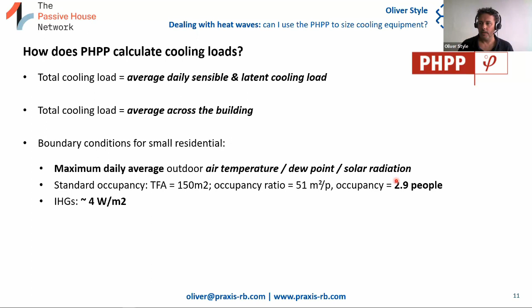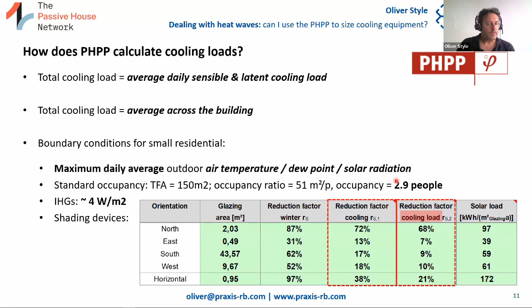And then shading devices. The PHPP calculates a reduction factor for the cooling load that actually assumes that people close the blinds more because it's too hot, and takes that into account for the cooling load. Okay, which you could say is a reasonable and logical assumption. But it's also possible that people don't drop the blinds. They forget to, or there's no control system that does it automatically, or simply they've been away for the weekend and they forgot to pull the blinds down, and they get back on a Sunday afternoon and the whole place is roasting. So it's important to understand what these base boundary conditions are for the PHPP, because they may not correspond to, will often not correspond to, what people will do in a home, and what you need to bear in mind when you're sizing the cooling plant.